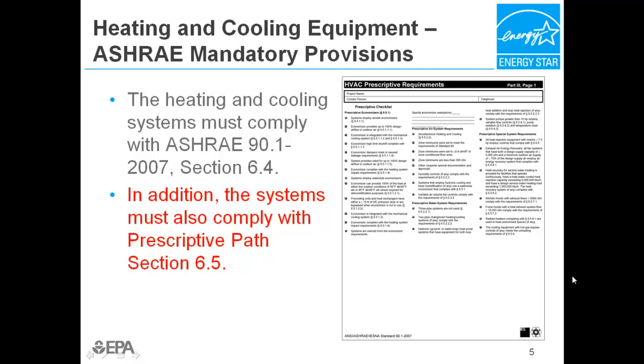ASHRAE provides a 2-page checklist that can help you verify whether the building has met those mandatory provisions listed in Section 6.4. For projects following the Prescriptive Path, compliance with Section 6.5 is also required. An additional 2-page checklist is available to verify compliance with this section. Neither of these ASHRAE checklists are required to be submitted to the EPA, but are available to assist the design team in ensuring that these requirements are being met.